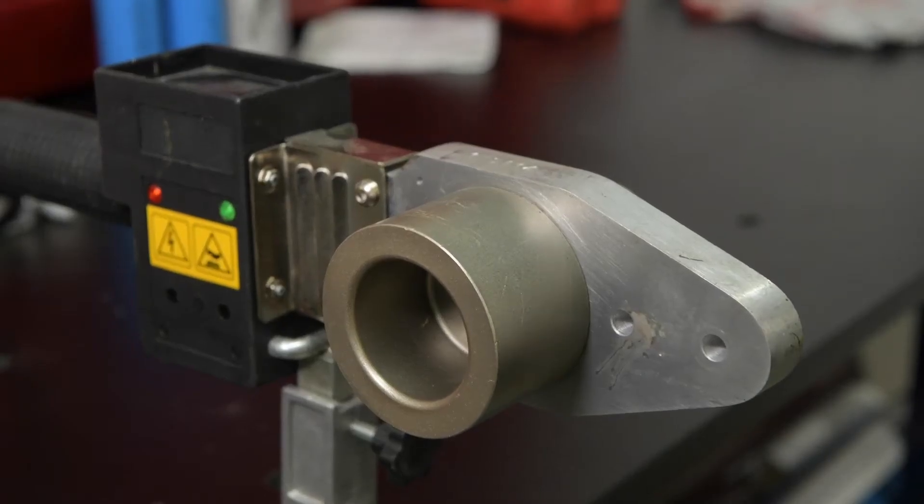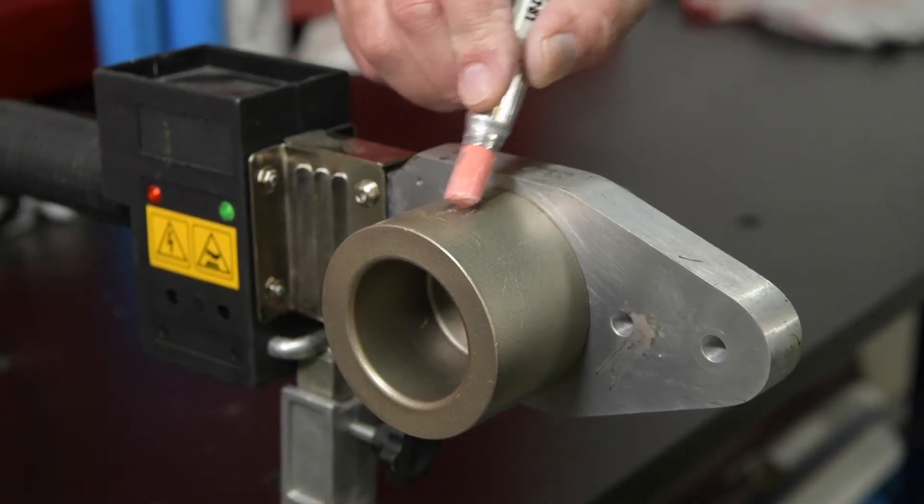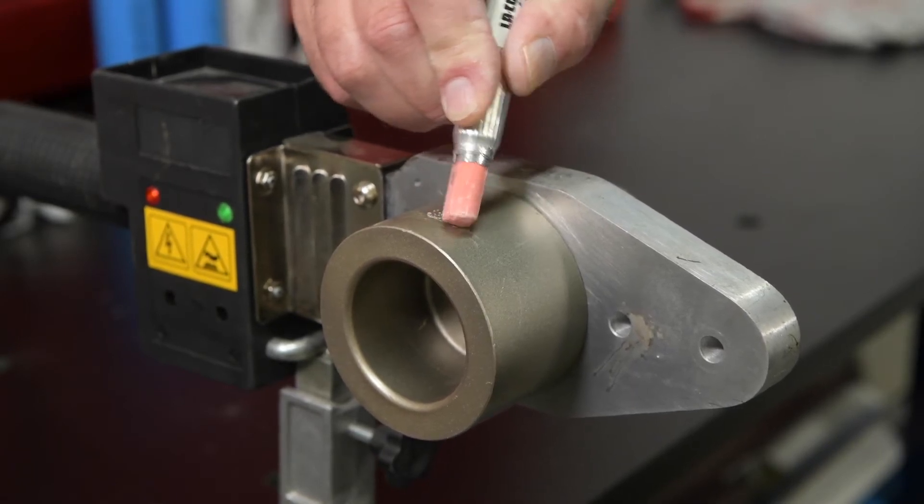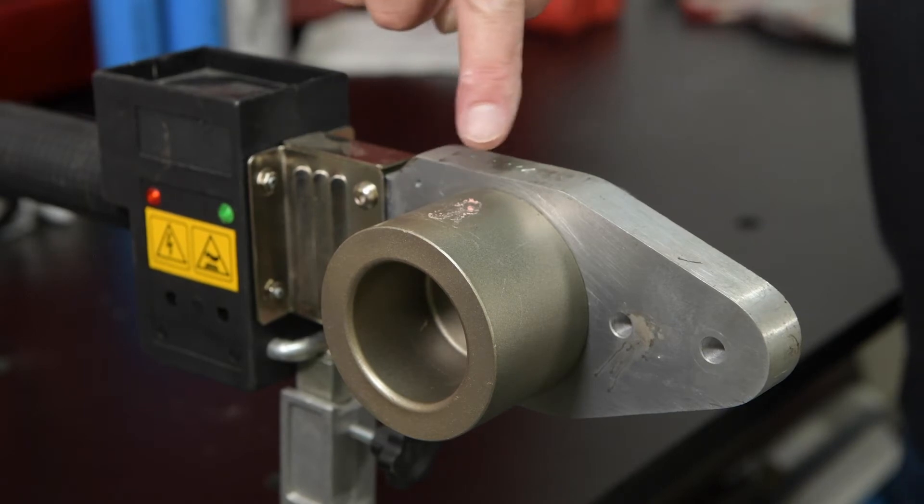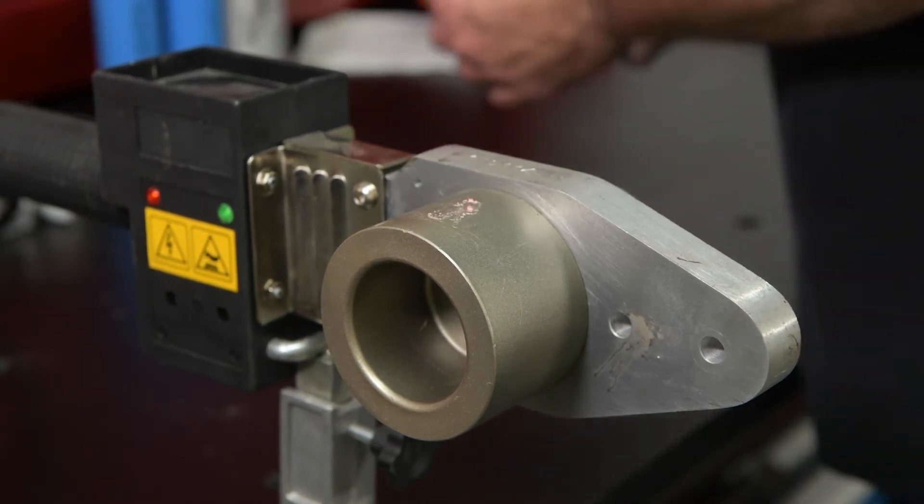Verify the temperature of the socket fusion tool using Tempil sticks. After plugging in the fusion tool, mark the outside of the female tool head. When the mark discolors and melts, the tool is ready for fusion.